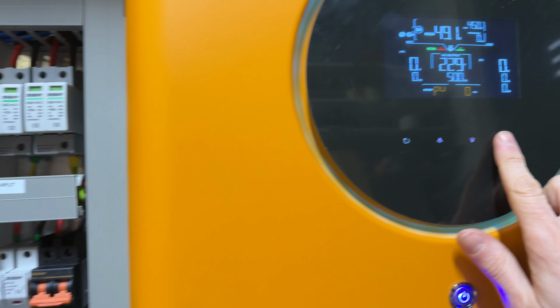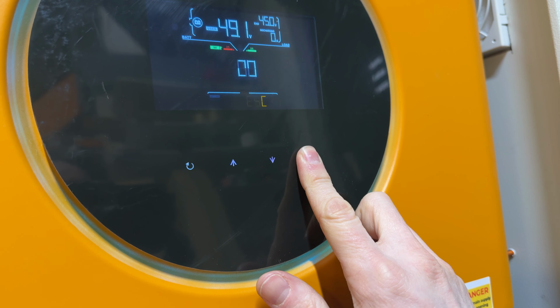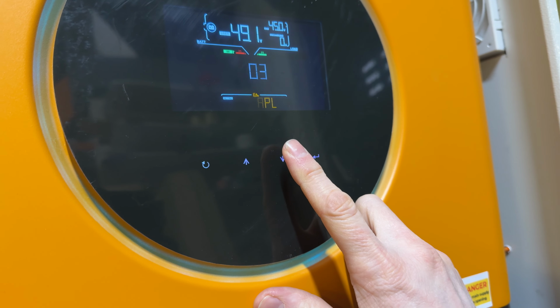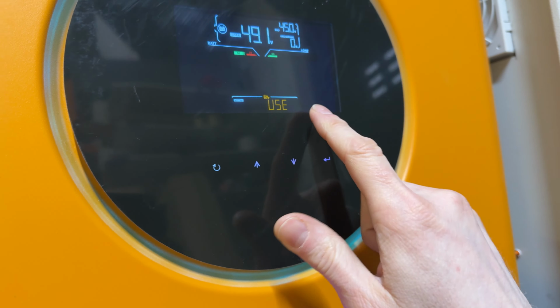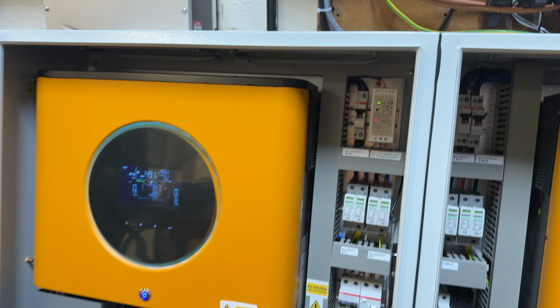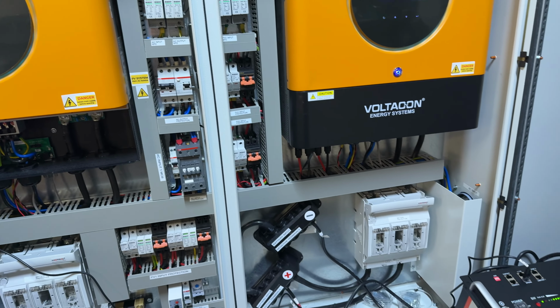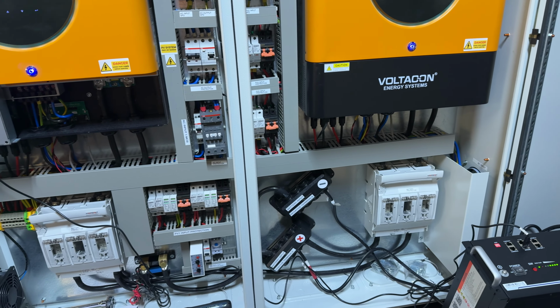And on the secondary inverter, menu 5 should be set to user, USE mode. That way the inverters communicate with the BMS of your lithium-ion battery. So that is how it works. If you have any doubts, please contact us and we will try to assist you. Thank you.